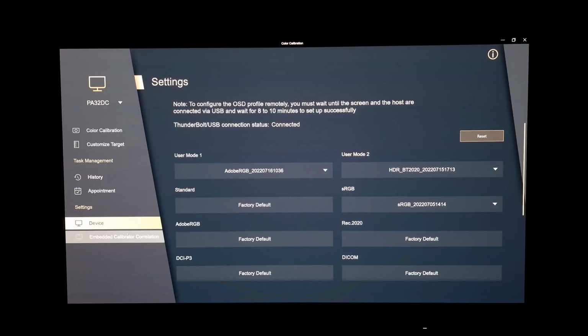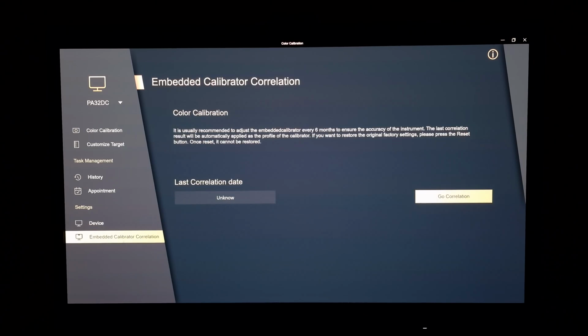The final thing, this isn't going to apply to any model at the moment, but the PA32DC or any model in the future which they decide to put this internal calibrator on. And I honestly hope they do, because I think it's a really neat feature. This is designed to calibrate the Calibrator. So colorimeters, they do drift over time. So to maintain the accuracy of the embedded Calibrator, they recommend that every 6 months you do a correlation with sort of a reliable external colorimeter.